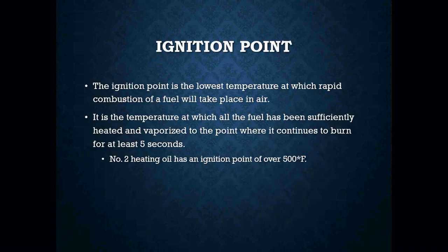Ignition point is the lowest temperature at which rapid combustion of a fuel will take place in air. It is the temperature at which all the fuel has been sufficiently heated and vaporized to the point where it continues to burn for at least 5 seconds. So number 2 heating oil has an ignition point of over 500 degrees.